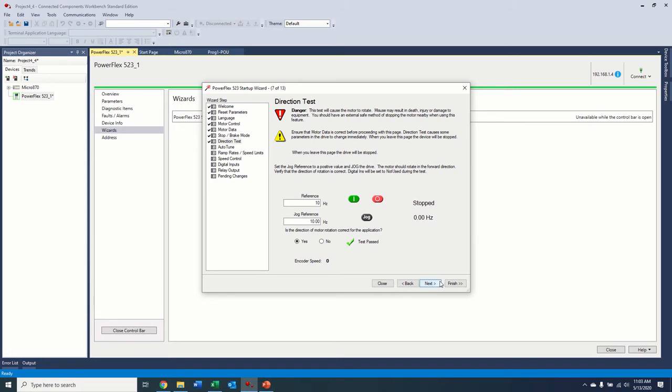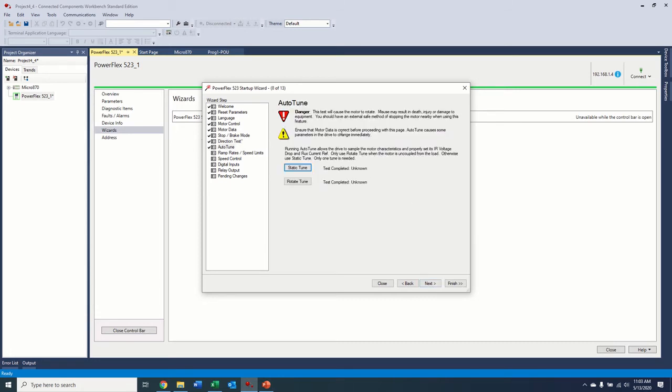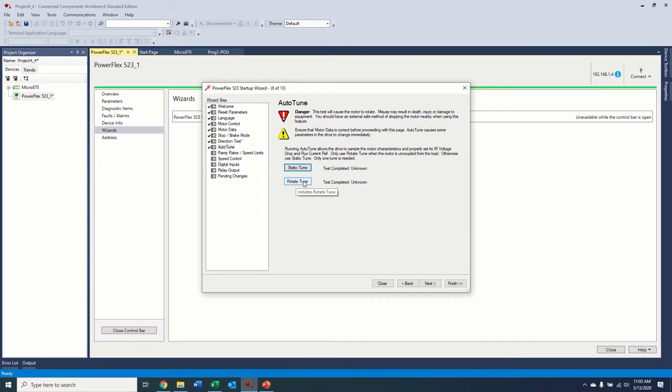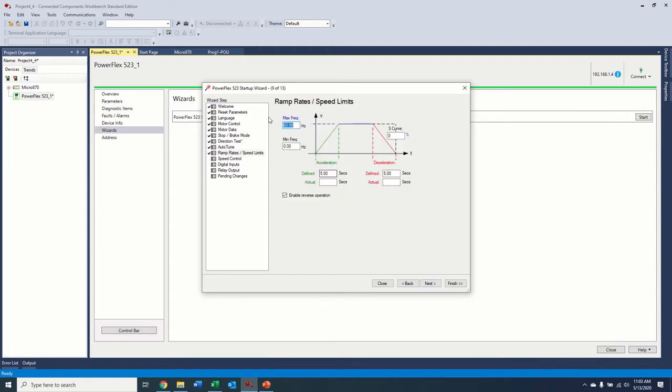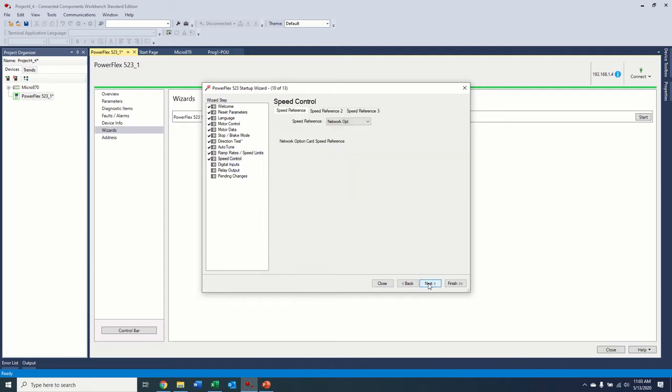The next step would be to do an auto tune. We're not going to do that here. But a static tune and rotate tune, rotate tune will move the motor. So you want to make sure it's uncoupled. Static tune will just not move the motor, just read the windings resistance. Ramp rates. So zero to 60 hertz, five seconds. That's pretty standard. But if you had any changes to that, you could set it here.